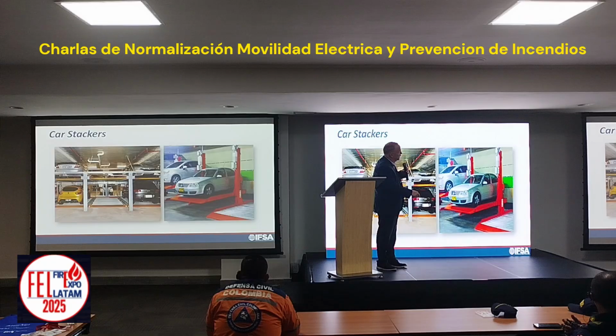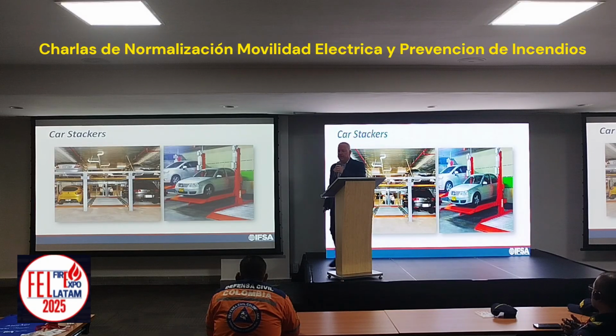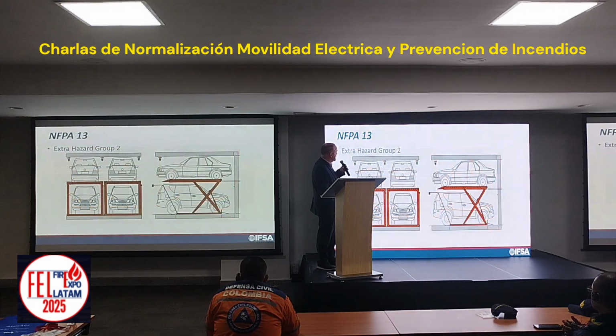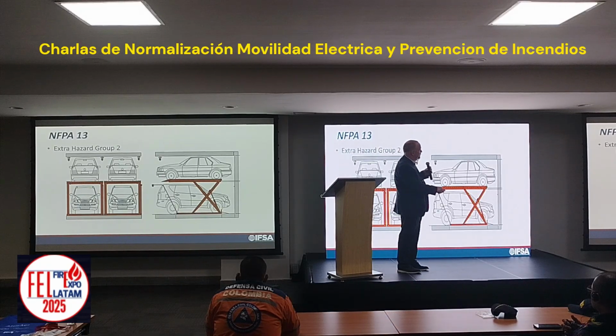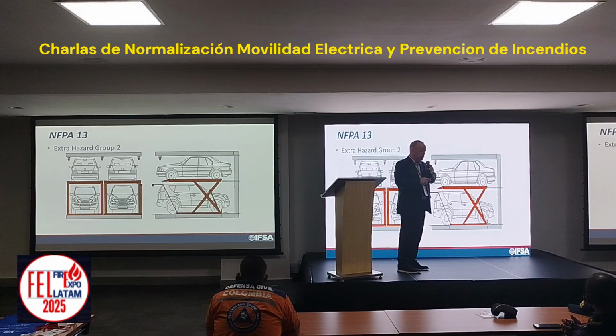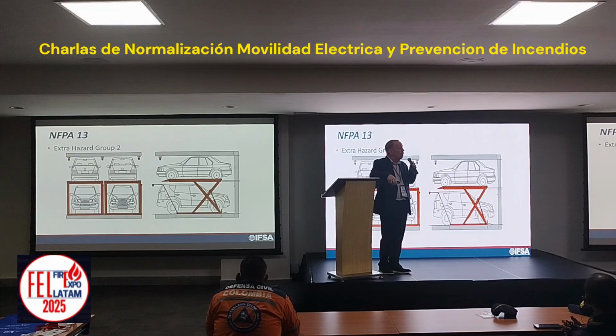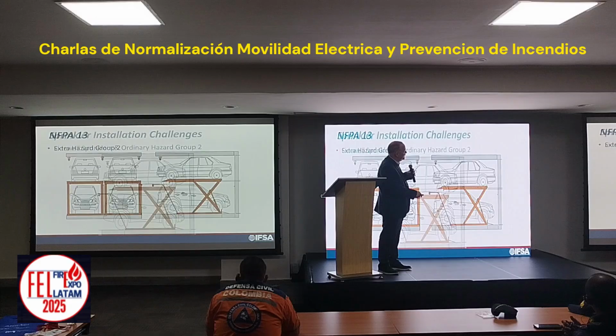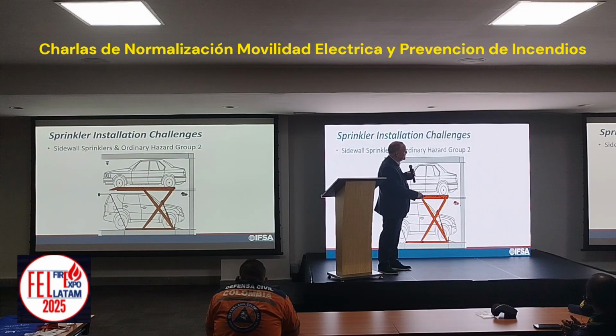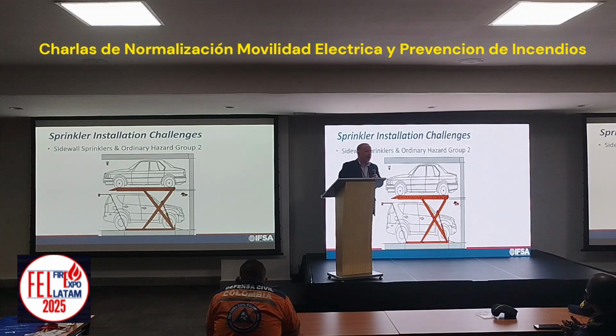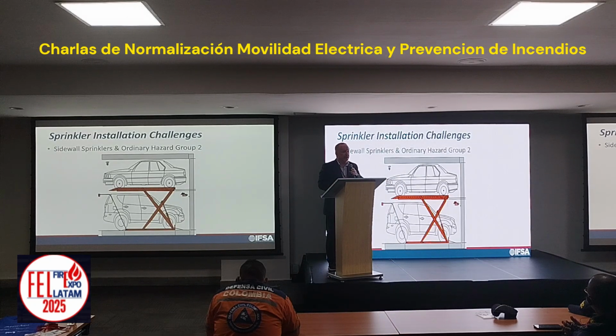The automobile or even the shelving here can cause the system to be blocked, the water spray completely blocked. One of the design parameters, by putting sprinklers up in here, it's extra hazard group 2, which is considerably more water than a standard ordinary hazard occupancy. But we can set it up with sprinklers at the ceiling, or sprinklers at the ceiling plus a sidewall sprinkler underneath to provide protection there.